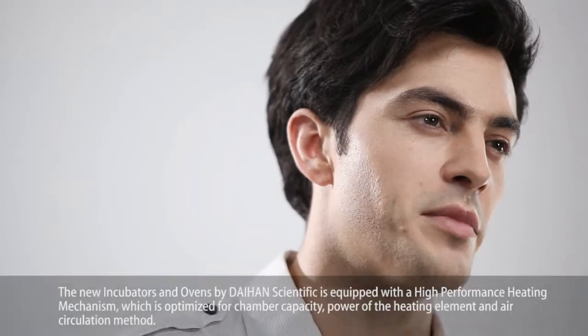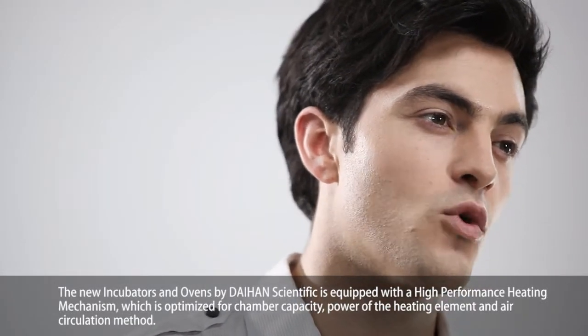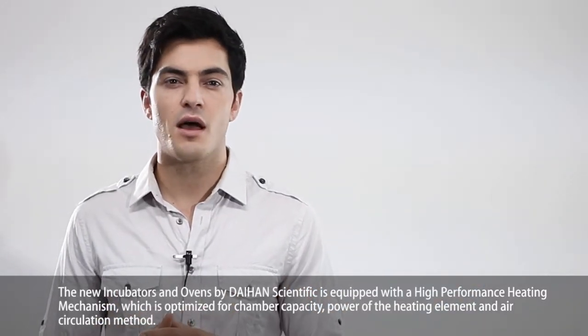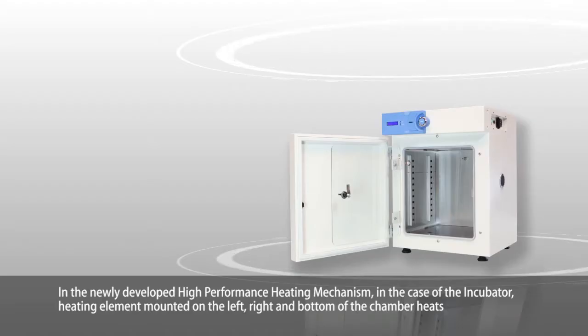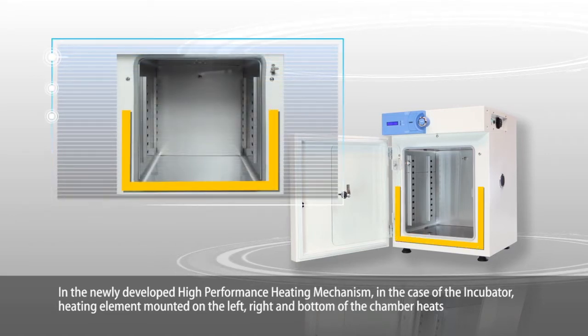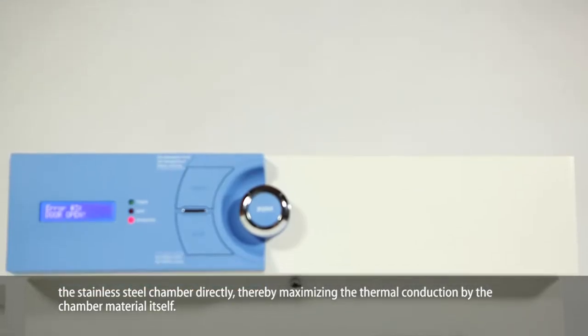The new incubators and ovens by DAIHAN Scientific are equipped with a high-performance heating mechanism optimized for chamber capacity, power of the heating element, and air circulation method. In the case of the incubator, heating elements mounted on the left, right, and bottom of the chamber heat the stainless steel chamber directly, thereby maximizing thermal conduction by the chamber material itself.